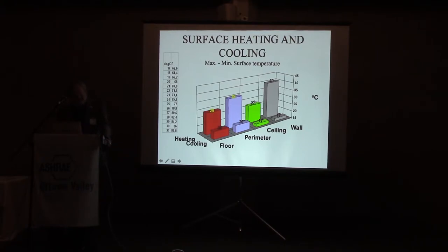For the cooling part, as I said, people are not so sensitive to cool radiation from above. So here the limiting factor will be the dew point. I have put it here as 17 degrees, but it depends, of course, on what humidity load you have on the building. And for the wall, again, for cooling, it will be the dew point. And there's discussion about how high a temperature we can get to on the wall. Normally we do not have contact with the wall. The pain limit, if you have contact with the surface, is about 43 degrees centigrade. But the wall should not be too warm, also because of the heat loss to the backside. So there's no really fixed limit for that. I recommend normally no higher than 40.